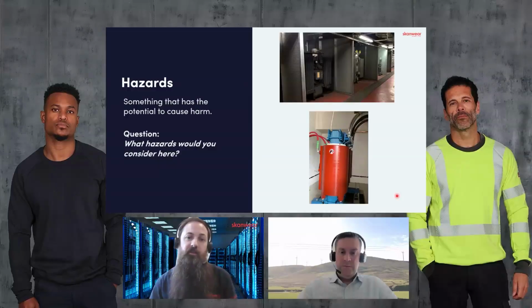Exposed conductors, definitely. Poor lighting - terrible in that location. And then obviously you've got a large accumulation of oil in that compartment. The one on top, there's something like 15 transformers in that one compartment, so there's quite a lot of oil to potentially accumulate. That's why that customer's put in fire barriers between each transformer. Yeah, definitely a massive point.